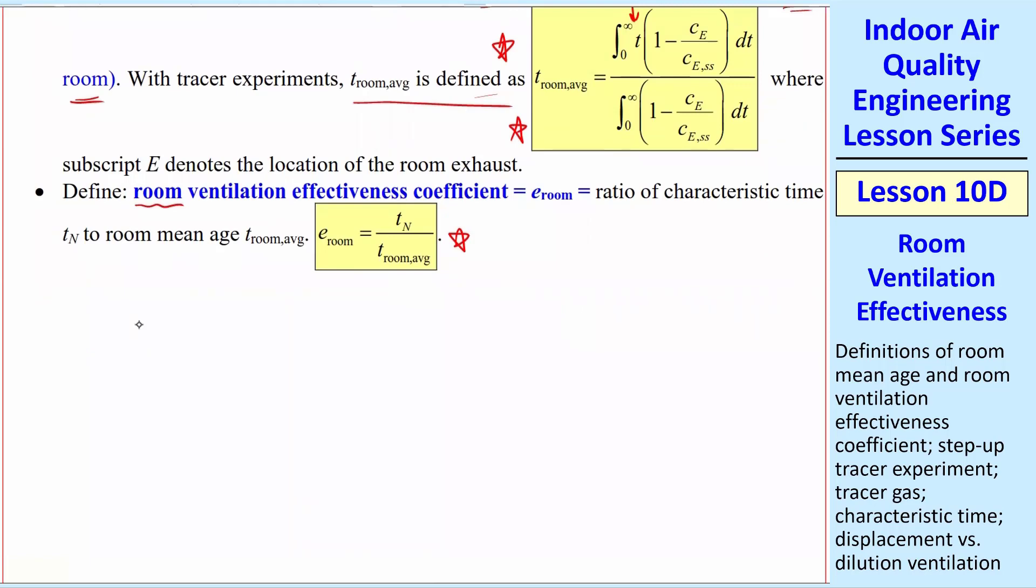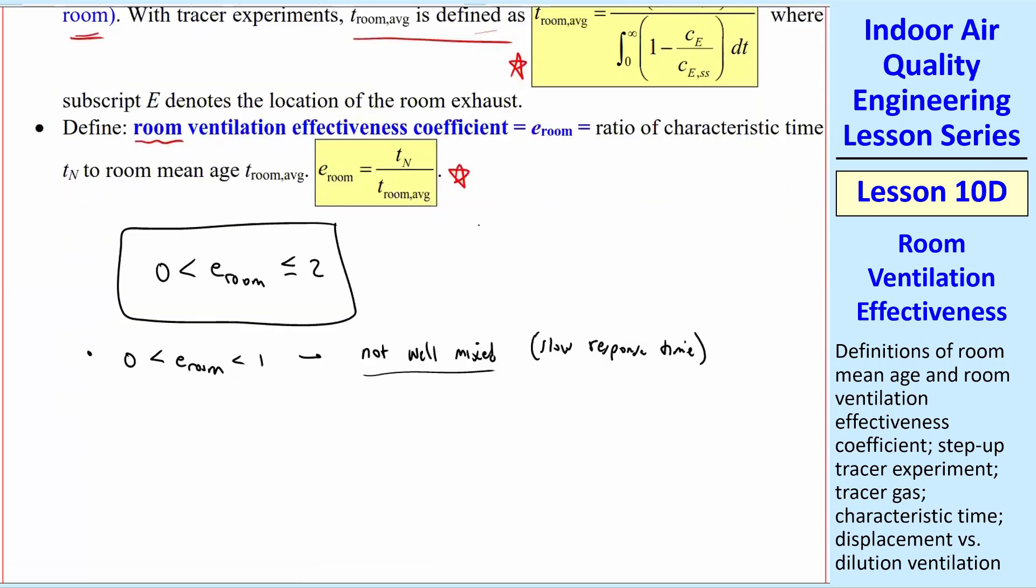Some comments. It turns out that E room varies between 0 and 2. If it's between 0 and 1, that means it's not well mixed. In other words, the room as a whole has a slow response time. So you have a ventilation system, and you don't have any kind of fans or something. There's nothing moving the air around. You're going to have pockets where it's very high concentration, pockets where it's low concentration, so it's not well mixed. We know that if we have E room less than 1.